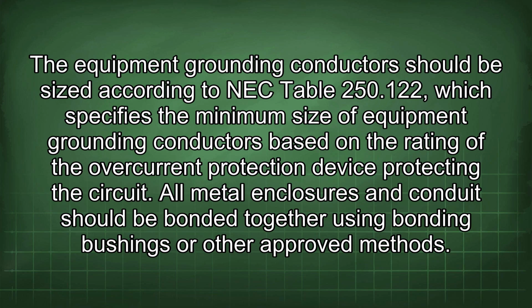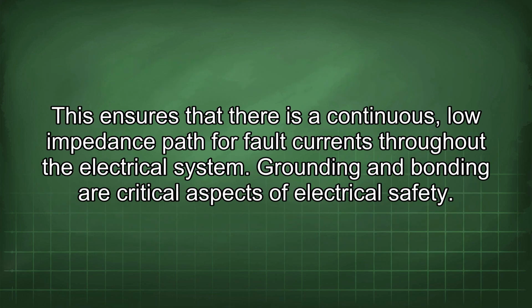The equipment grounding conductors should be sized according to NEC Table 250.122, which specifies the minimum size of equipment grounding conductors based on the rating of the overcurrent protection device protecting the circuit. All metal enclosures and conduit should be bonded together using bonding bushings or other approved methods. This ensures that there is a continuous, low impedance path for fault currents throughout the electrical system.